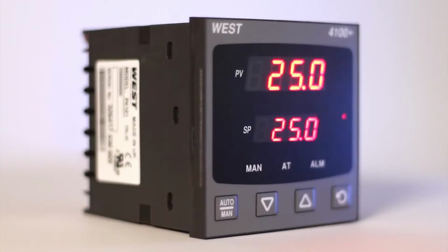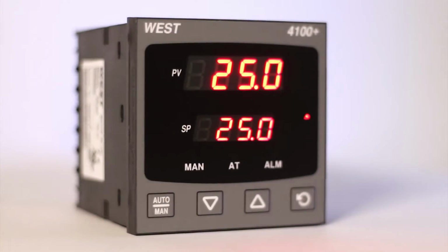So you can use a deviation alarm to warn you if your process is getting too high or if it is getting too low. But what if you wanted to know if it was too high or too low? If your controller has more than one alarm available, you can set one up as a deviation high alarm and the other as a deviation low alarm, so that you'll receive a warning if there is a problem in either direction. If, as in the example I just gave, you wanted alarms at 225 degrees and 217 degrees with a set point at 220, this is exactly what you would do.